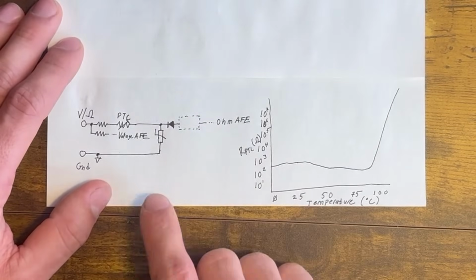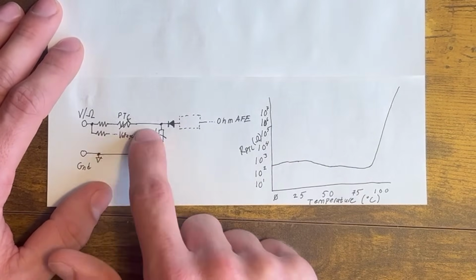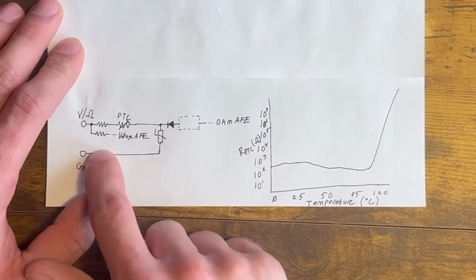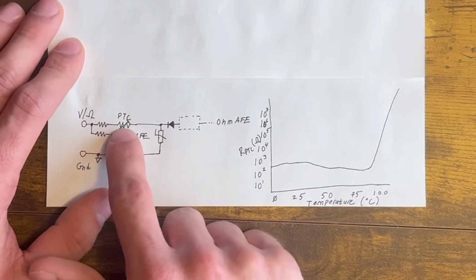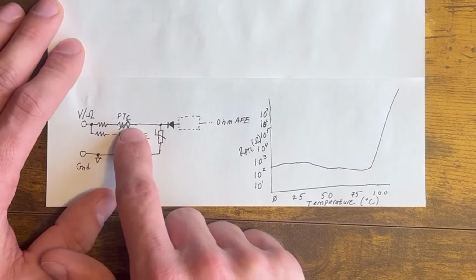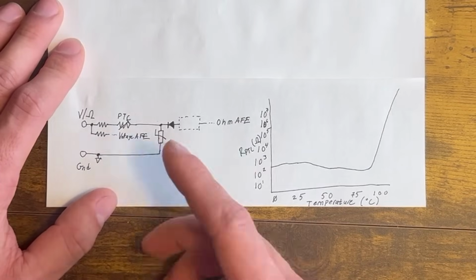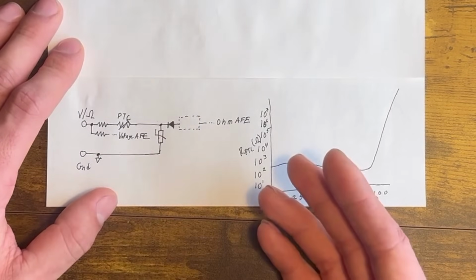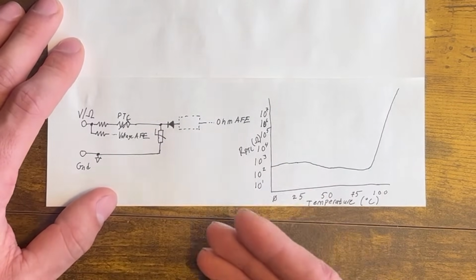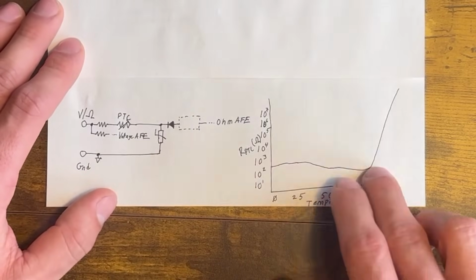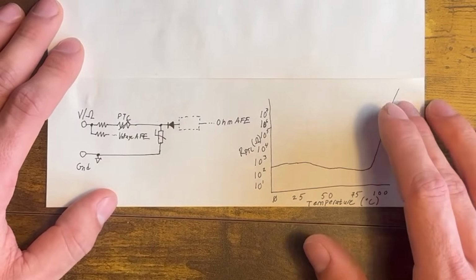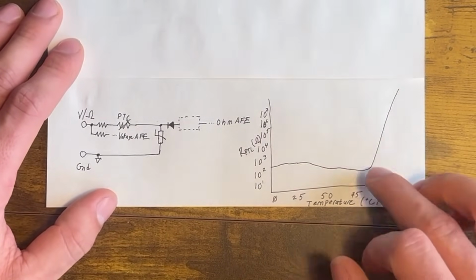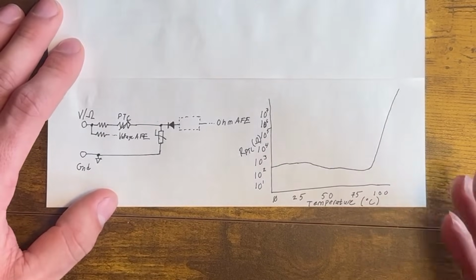During an overload, current flows through this front end into the MOV and back out, so any voltage above the MOV voltage gets dropped by the PTC, and that can put a lot of power through it very quickly. Dissipating power in a part makes it heat up, so this heats up, at some point resistance shoots up, drops the current, and so drops the heating, and it will eventually equalize to some tolerable amount of power.